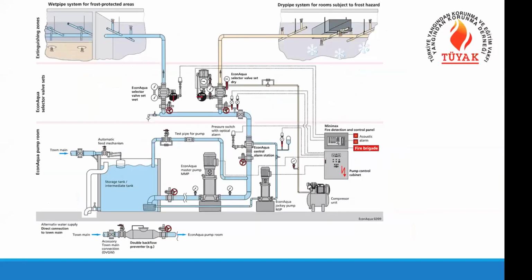So in that schematic, you will see a combined system. So there is a water tank, fire pumps, and sectional valves, which are called alarm valves. And if you have a system with freezing temperatures, you have a dry system. So you cannot keep water inside the freezing rooms that are below 4 degrees Celsius. In cold rooms and cold storage areas, you have to have dry systems. And the wet systems are only inside the normally heated areas or normal rooms, not in unheated or freezing temperatures.